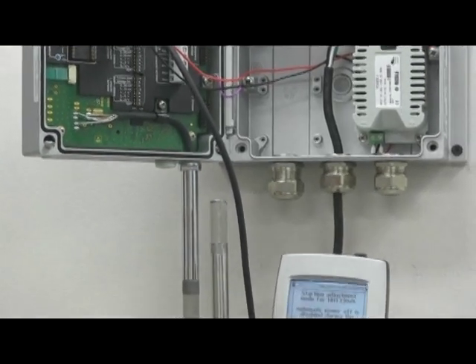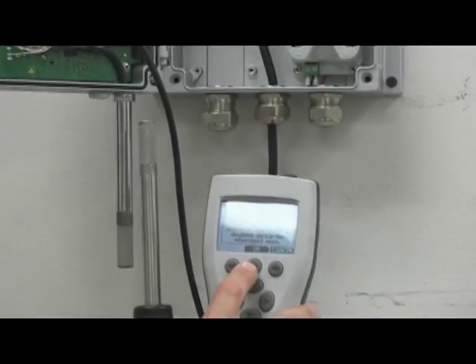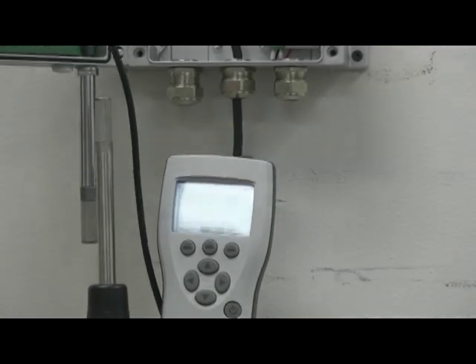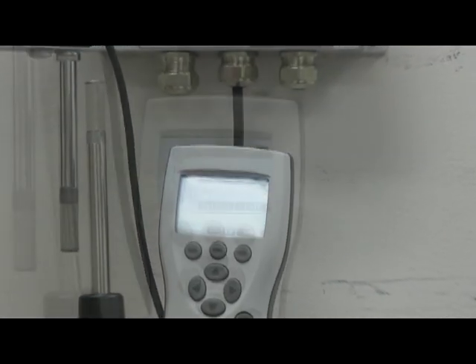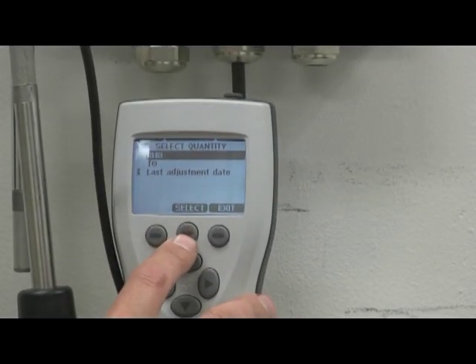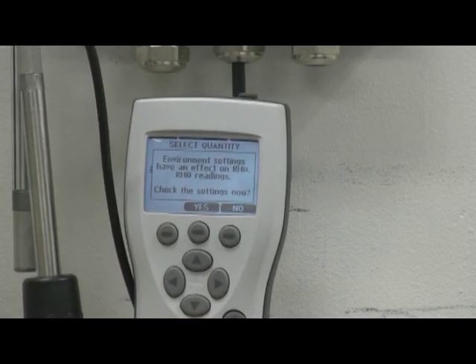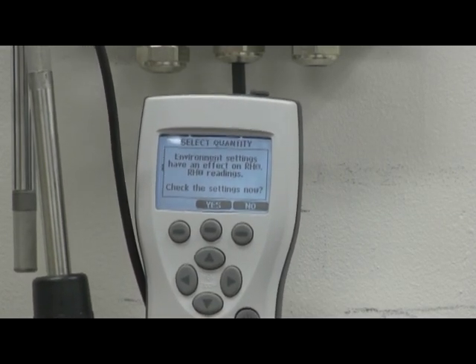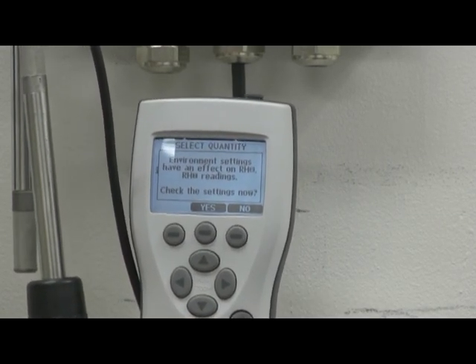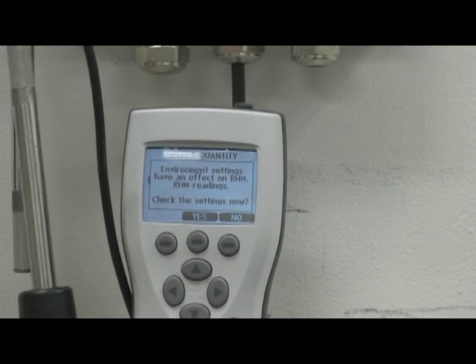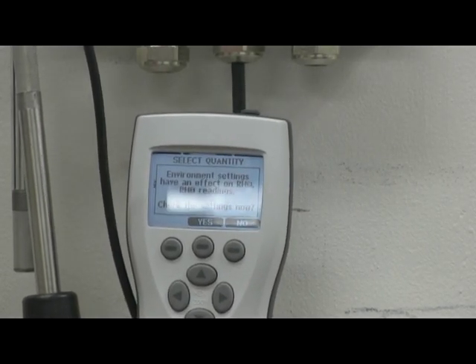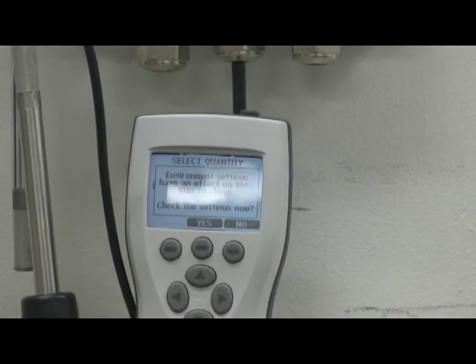Step 4. Press OK and select RH. Now you'll see the message environmental settings have an effect on RH, check settings now. This is simply verifying that the sensors are both at atmospheric pressure and not at different pressures, so we select no.